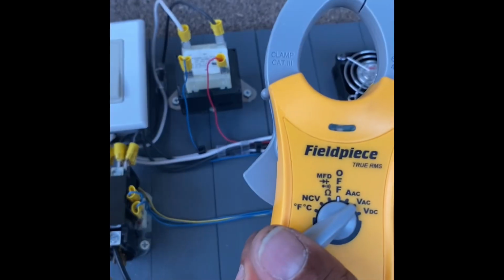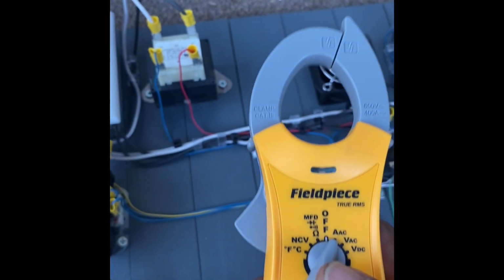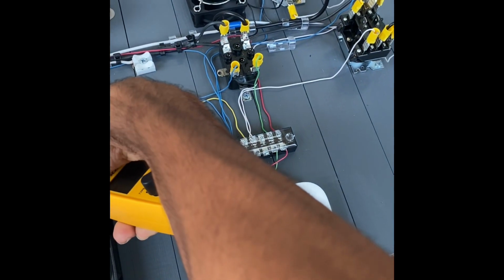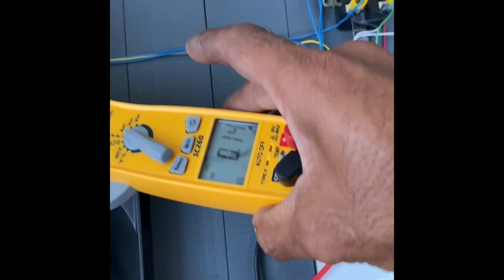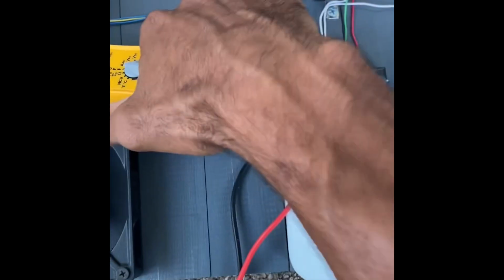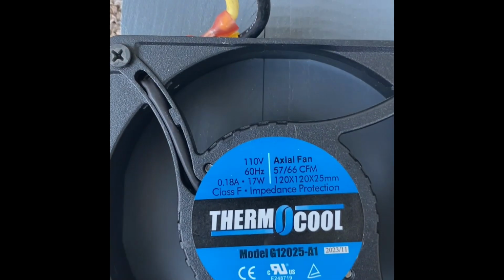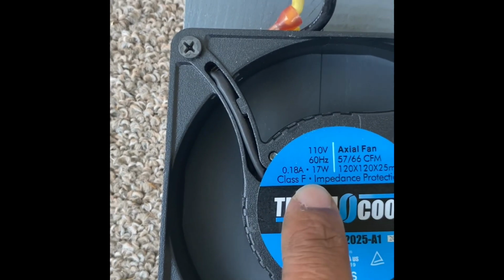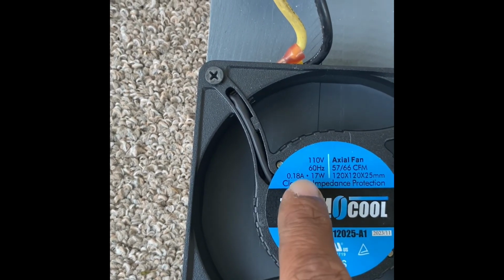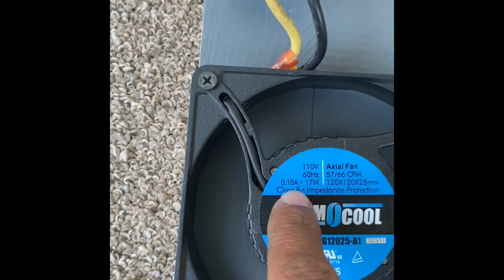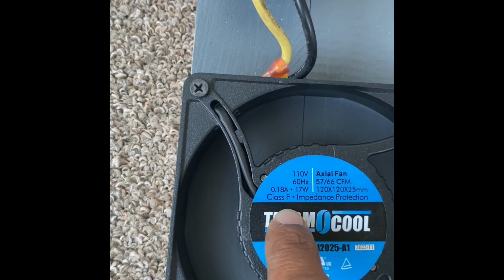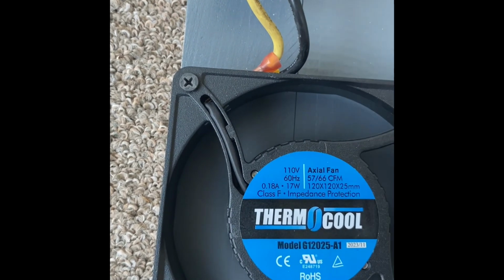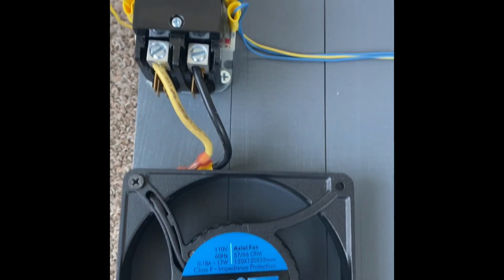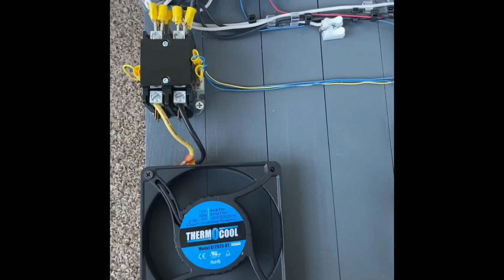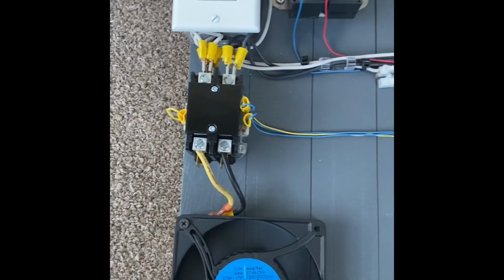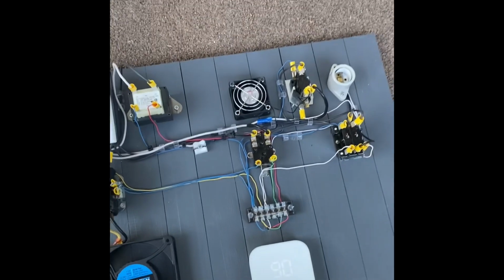Now, let's check the amperage of that unit. So we all know the amperage is this button right here. We're gonna put the clamp around the wire, and we're checking amperage, and we got 0.11. Now the rating for this motor is 0.18. Always remember, you want to have amperage below that number. You don't want it to be over amperage. So this is good right now, right? So we already know how to use the multimeter, checking voltage and checking amperage.